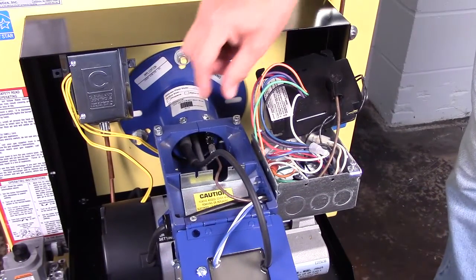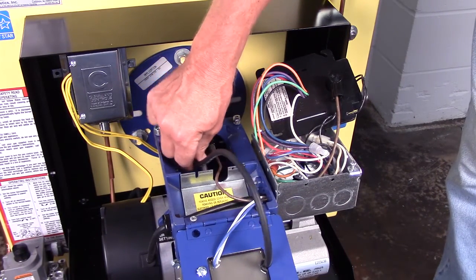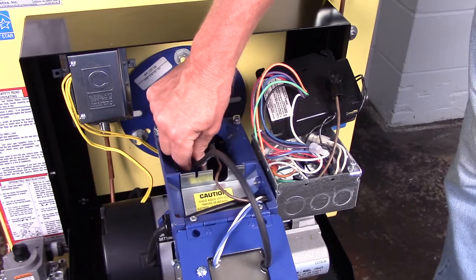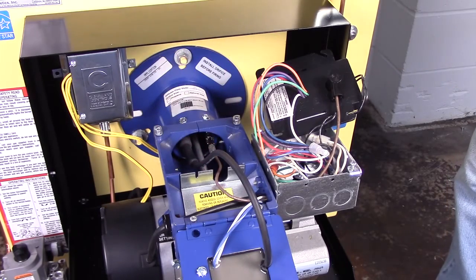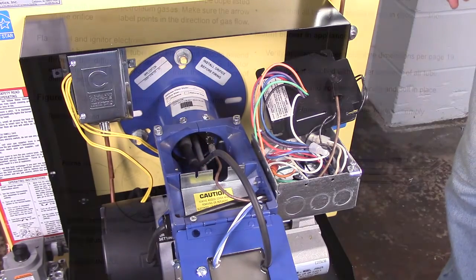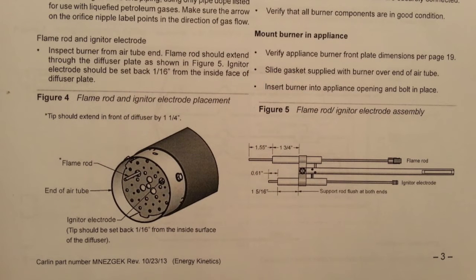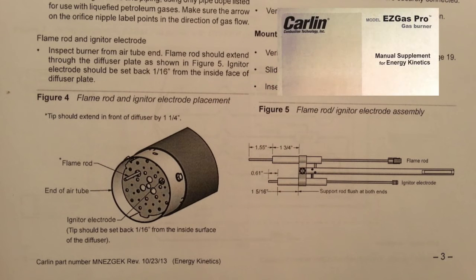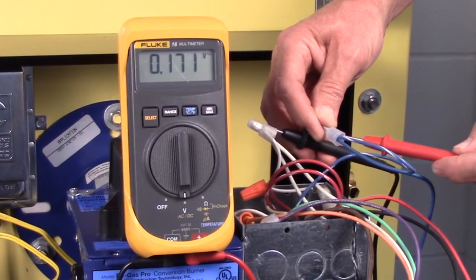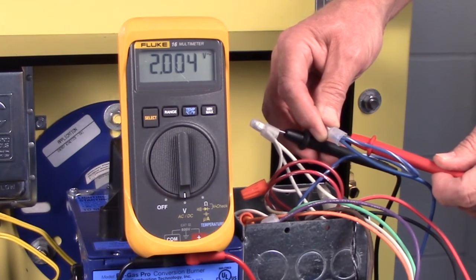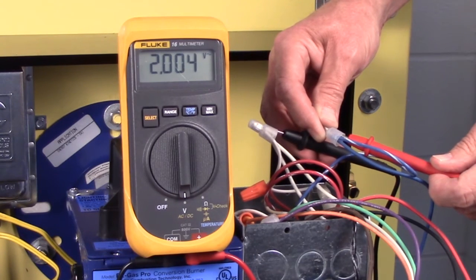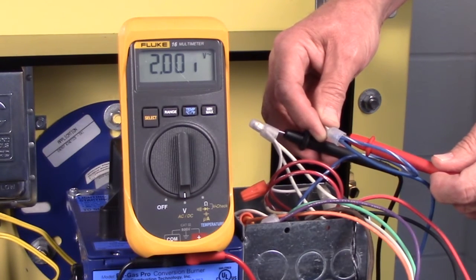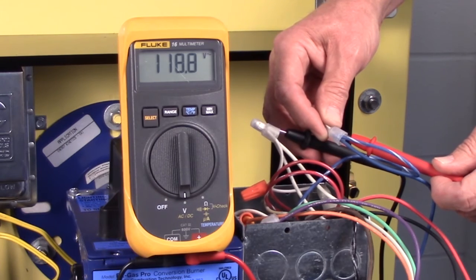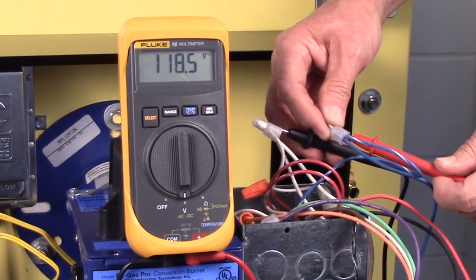If light off is still an issue, you should check the igniter cable connection to the spark electrode and the position of the igniter electrode. For correct settings, see page 3, figures 4 and 5 in the EZ Gas Burner Manual Supplement for Energy Kinetics, and adjust if necessary. Also check the primary voltage to the igniter. If 120 volts AC is present to the igniter and it doesn't generate spark, replace the igniter.